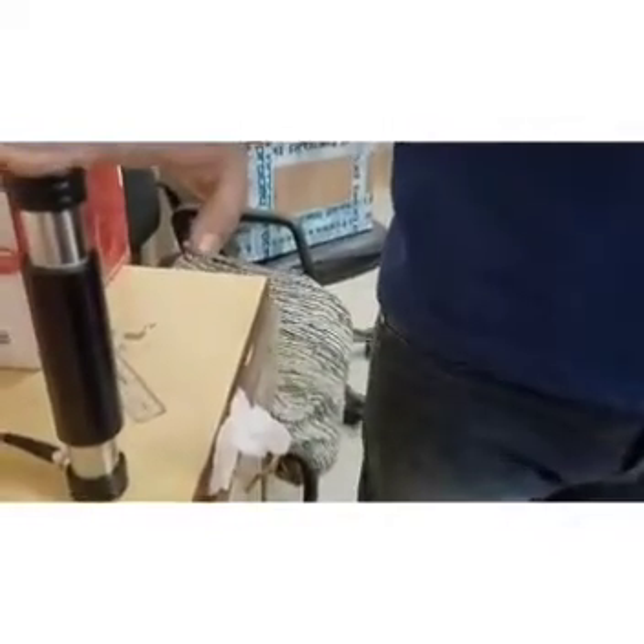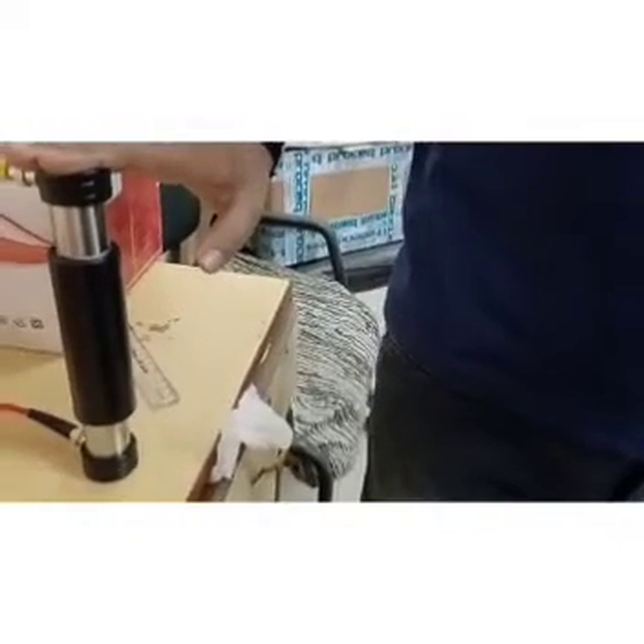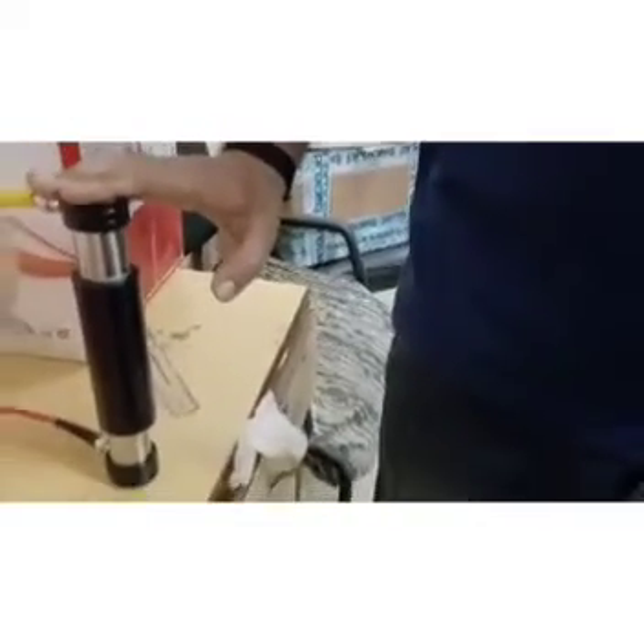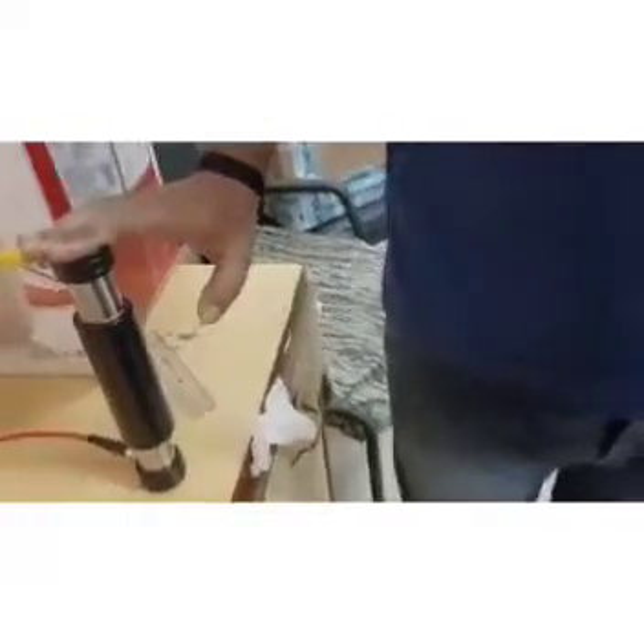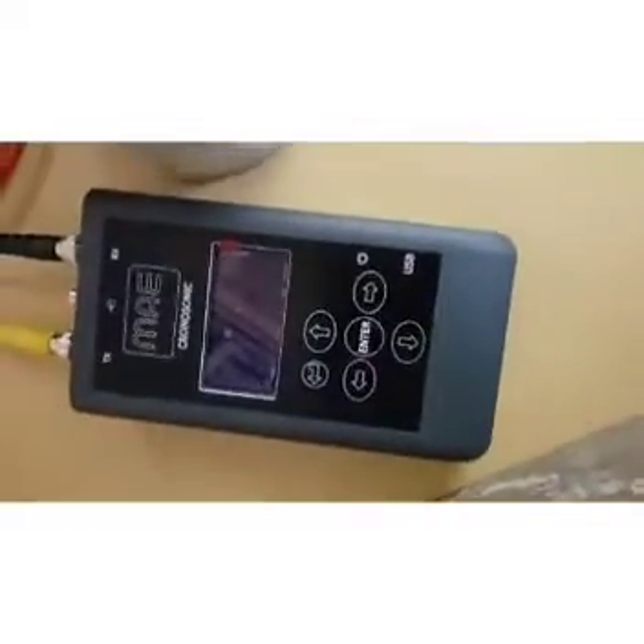Now we will check the calibration like this. You need to place a calibration bar between the two probes, one connected with the transmitter and one connected with the receiver cable that goes to the main unit, MAE Chronosonic.